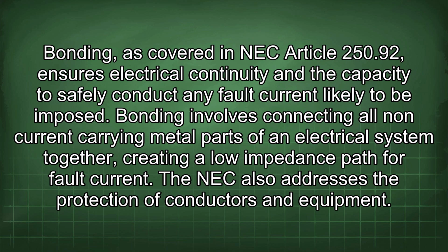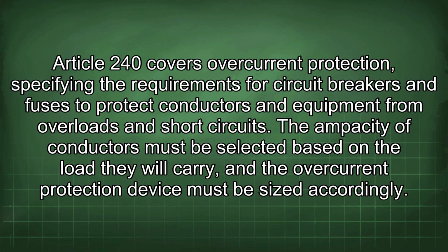path for fault current. The NEC also addresses the protection of conductors and equipment. Article 240 covers overcurrent protection, specifying the requirements for circuit breakers and fuses to protect conductors and equipment from overloads and short circuits.